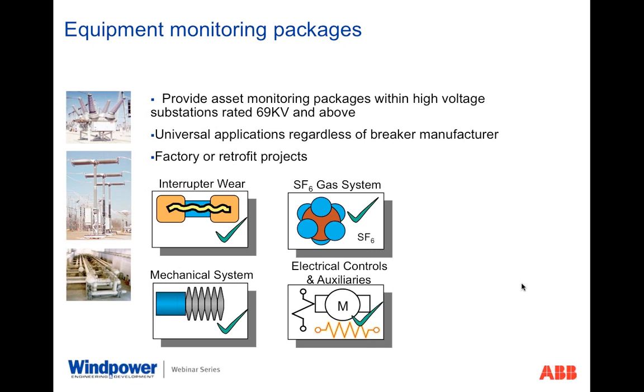As for the mechanical system, breaker timing parameters can be extracted using dedicated travel sensors or auxiliary switch timing methods. The CBS provides a travel curve to determine reaction time, mechanism time, total travel, and contact velocity. This is calculated every time the breaker operates to continuously capture and trend any mechanical changes. Finally, the electrical controls and auxiliary circuits include peripherals such as heaters, motors, motor run times, coil energization, and coil continuity, to ensure that when the breaker is required to operate, it will do so without a failure imminent in the design or aspect of that breaker.